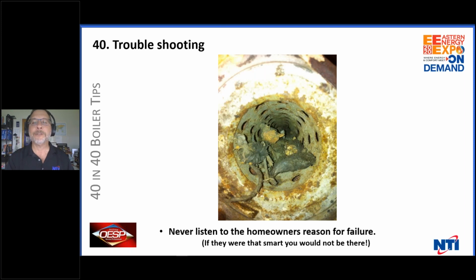And last but not least, troubleshooting. Never listen to the homeowner's reason for why the boiler failed. They'll tell you everything. They'll tell you exactly what happened to it. I've walked into houses where there's been legal sheets of paper taped to the wall, 10, 15 of them, exactly what was wrong with the boiler. If they're that smart and watched YouTube that much, then they should fix their own boiler. Though I don't suggest it. It's like giving somebody a gun that doesn't know which end to point. Don't do it.